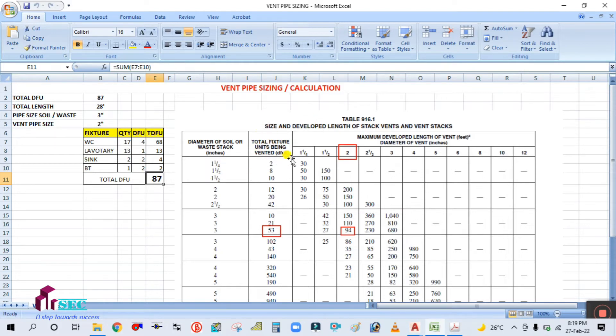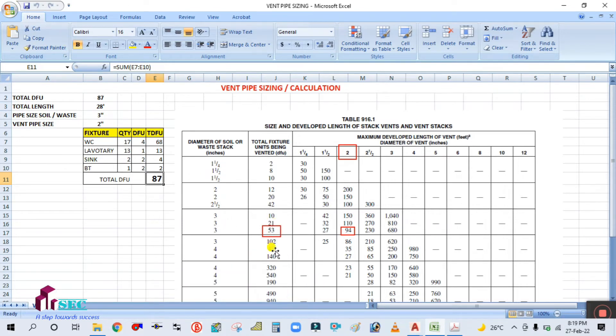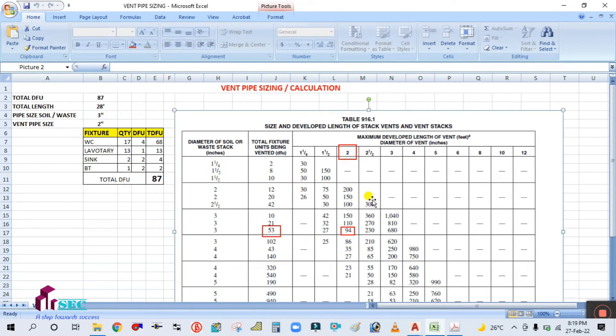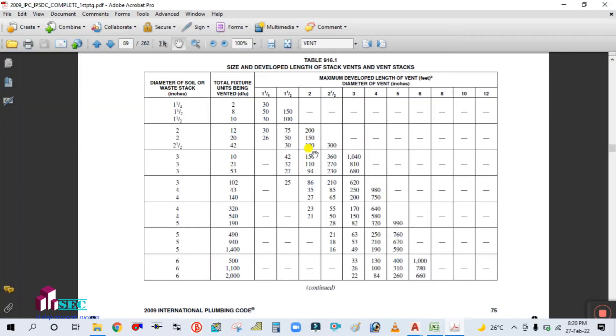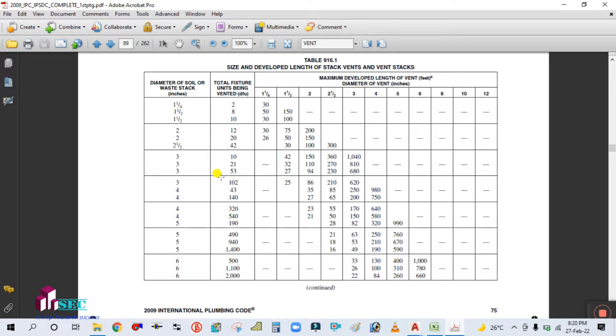In this table, in this column you are seeing the total fixture units being vented — that means the total drainage fixture unit. The total drainage fixture unit is 87. You have to find 87. Since 87 is not available, you will take the next maximum value. Go to Tools — total drainage fixture unit is 87.